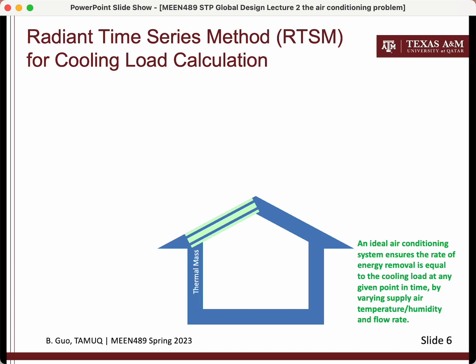The cooling load is time-dependent, so the ideal air conditioning system should be able to track a time-dependent rate of energy removal, though practically this is not possible. To provide space cooling, the air conditioning system causes airflow through the conditioned space. At the inlet the air is cool and dry — this is called the supply air. As the air flows through the conditioned space it gets warmer and more humid as heat is transferred from surfaces and water vapor is added. The air leaves with a higher energy content and is called the return air.